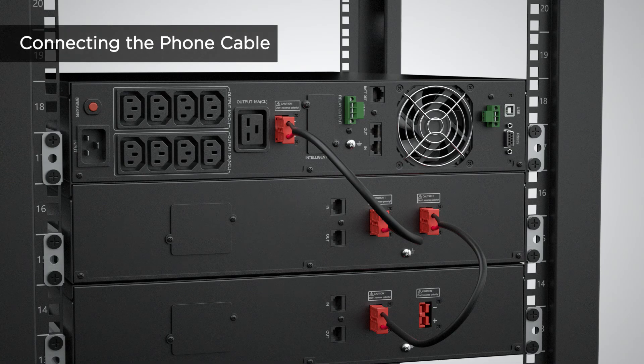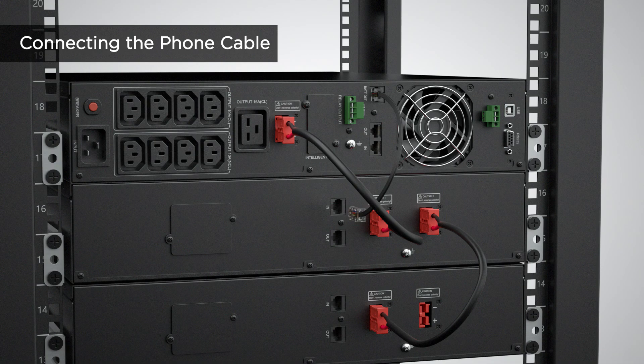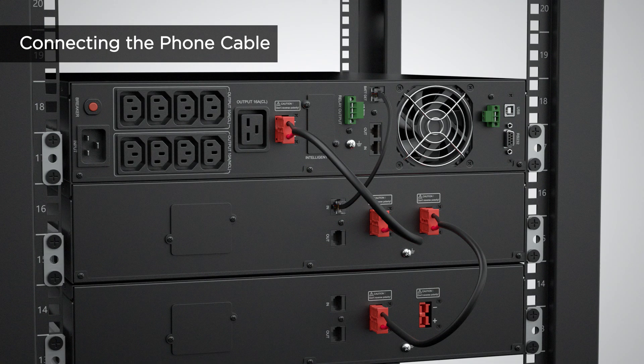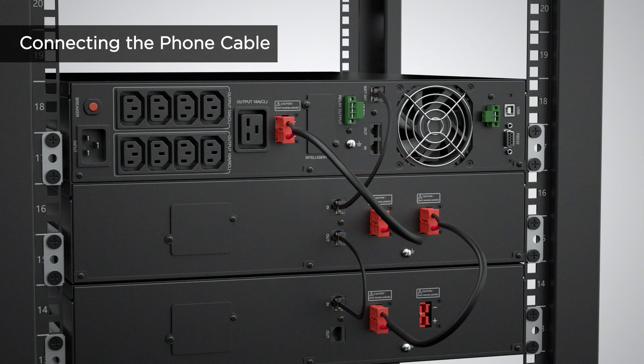For extended battery module detection, connect the phone cable to the battery detection port of the UPS and to the port marked with in of the first extended battery module. Then, use another phone cable to connect the port marked with out of the first extended battery module to the port marked with in of the next one. Repeat this procedure to connect all extended battery modules.